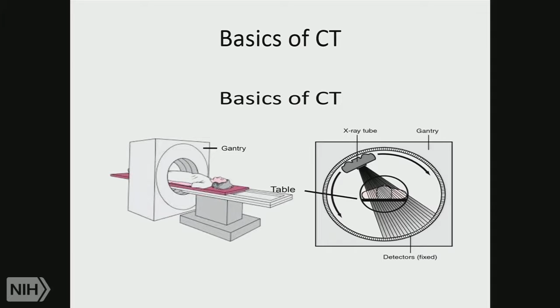And as you can imagine, from this idea of CT projection or filtered back projection, as you take multiple views of these 4 tubes, you will get different profiles depending on where you are. So at one point at this diagonal, you'll see 3 bumps. At this perpendicular, just 2. Again, 3 as you go this way, and 2 as you go up and down. And as you do this more and more, you'll begin to recognize the 4 tubes that are in there. And this is called filtered back projection. Now, there are many, many sophisticated image processing algorithms that clean up this image significantly. But this is the basis for the imaging.